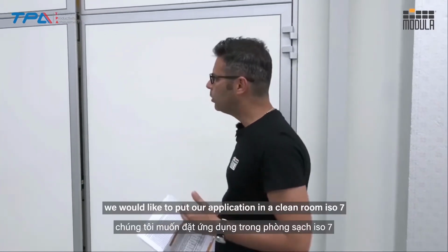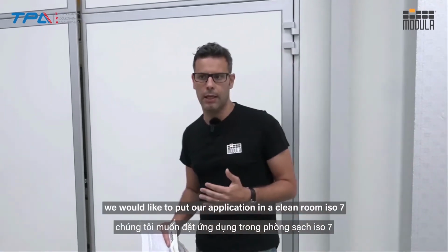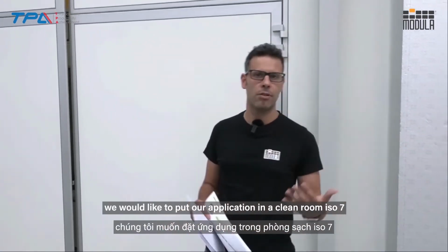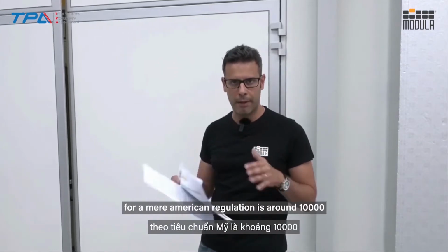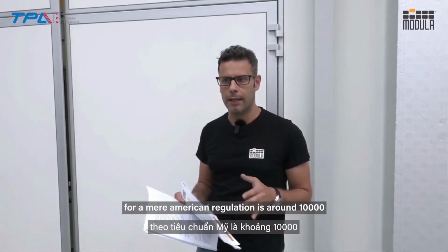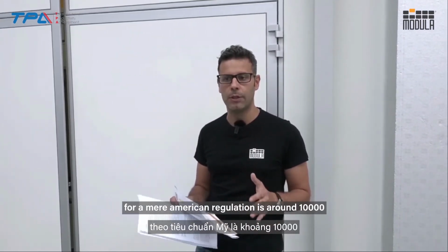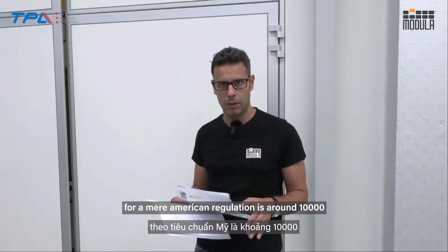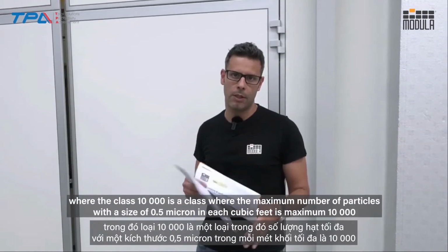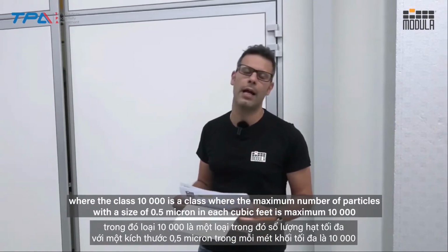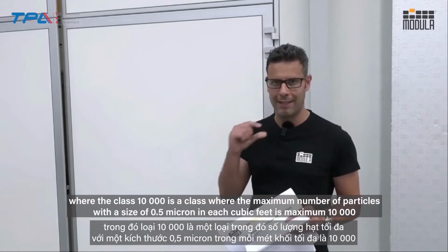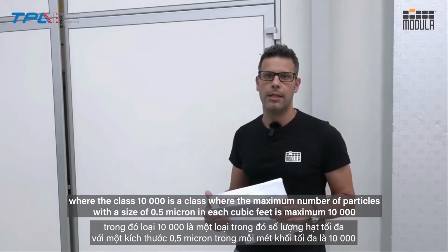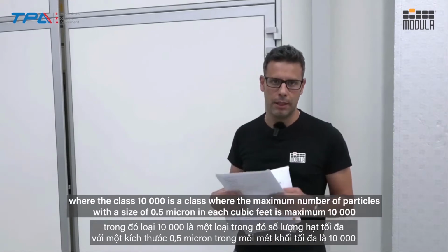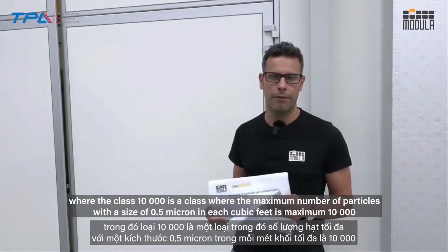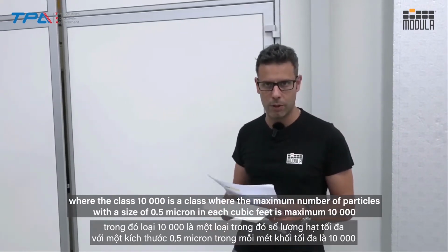We would like to put our application in a clean room ISO 7, which for the American regulation is around class 10,000. Class 10,000 is a class where the maximum number of particles with a size of 0.5 micron in each cubic foot is maximum 10,000.